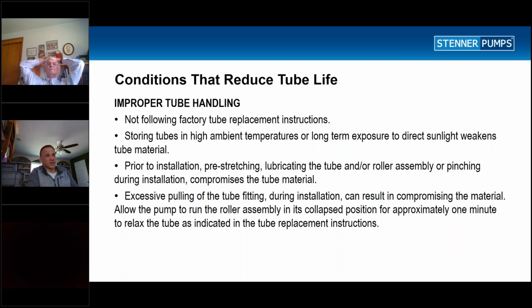Never put lubrication on it. We don't recommend that. I've had some people fill up the entire roller housing with lubrication. That's not necessary, and we don't recommend that. I had this come up one time. Customer was trying to loosen up the rollers, and they loaded the rollers up full of Vaseline. Vaseline is a petroleum-based product, and Santoprene does not work very well with petroleum-based products. So you can probably imagine how fast that tube wore out.